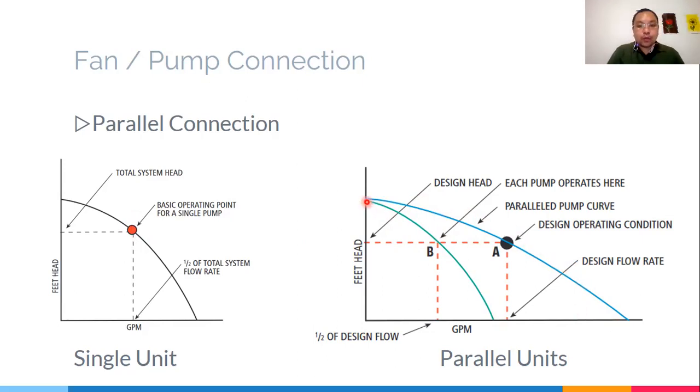Mapapansin nyo, no? When you connect pumps in parallel, the system performance curve goes farther, but the pressure remains the same. Only the flow increases, doubles to be exact, 100%, half of the design. So this length is equal to this length.